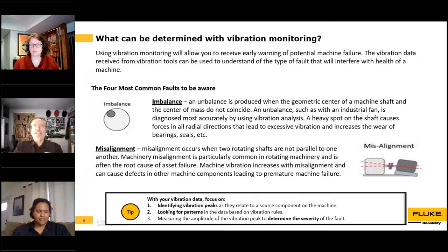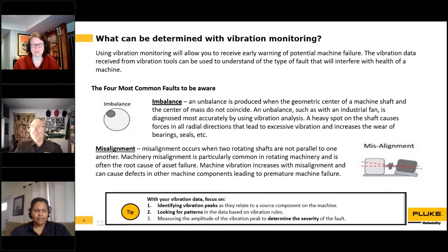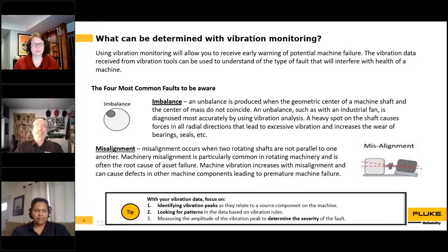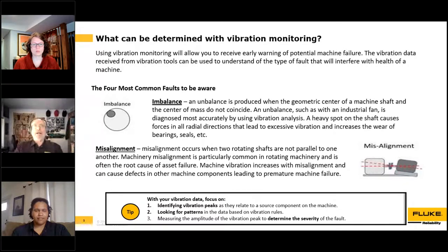Vibration analysis can be simplified to three steps. First, we identify the peaks inside the data to their source — for example, is that vibration coming from the rotating shaft? Second, we look for patterns in the data. Imbalance is going to be seen at once per revolution of the rotating shaft as that heavy spot comes around, seen in the radial direction — that's the pattern we look for. Finally, we look at the amplitude of the peaks and the increase in that pattern to determine how bad the fault is.